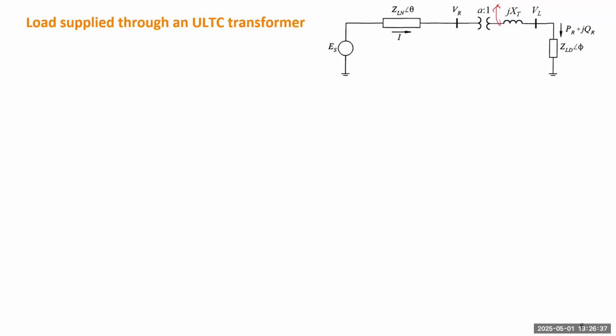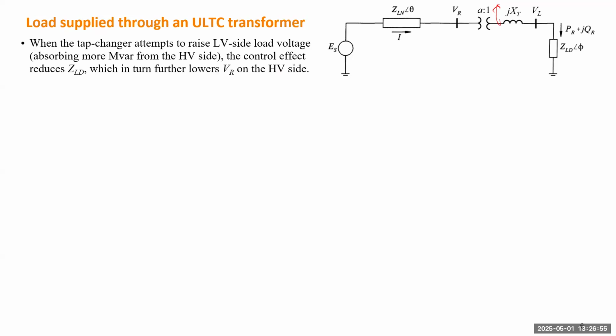But a transformer is not a reactive source. It doesn't provide reactive power. What it does is take some reactive power from the primary side and give it to the secondary side, and meanwhile it also absorbs more reactive power. It's like a broker. We already explained this one. But if we use an under load tap changing transformer to control voltage, it can become one of the main causes of voltage collapse because it's not a reactive source.